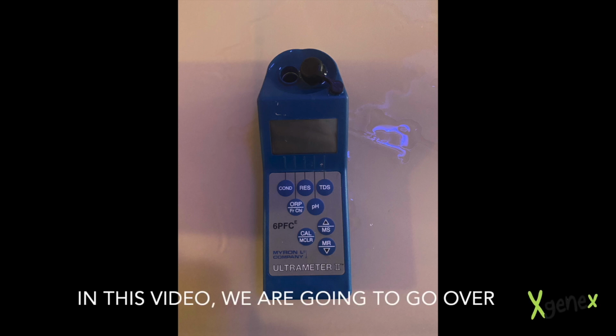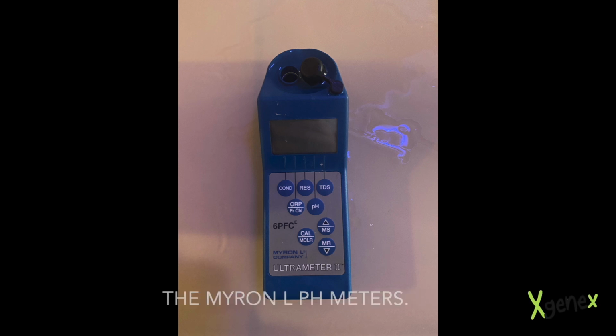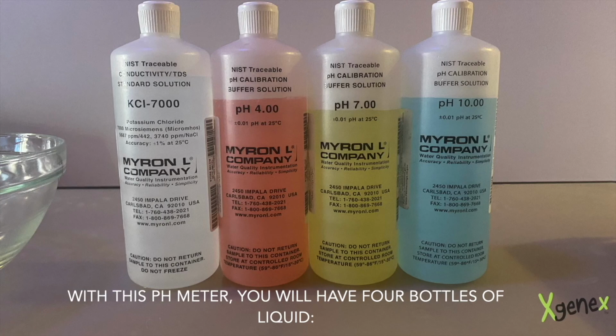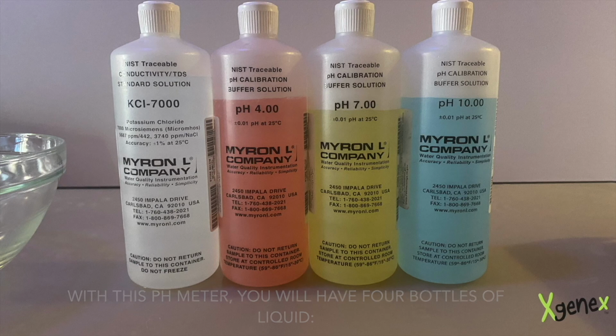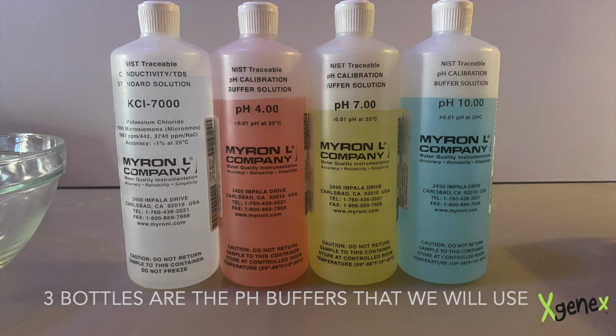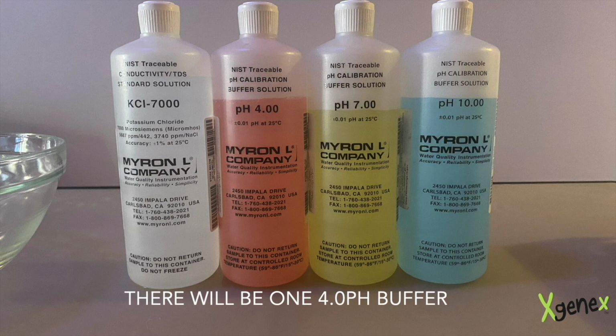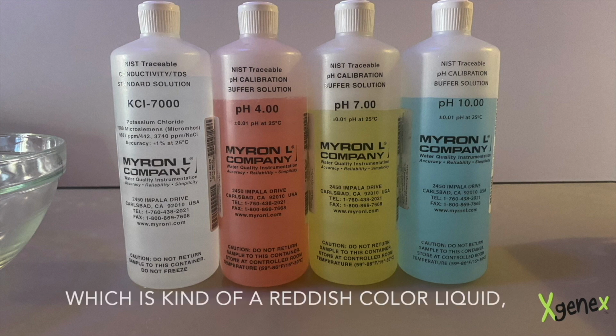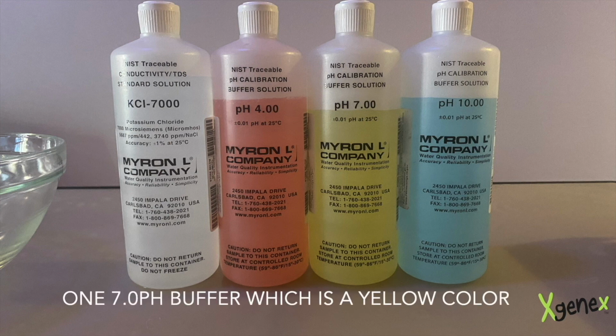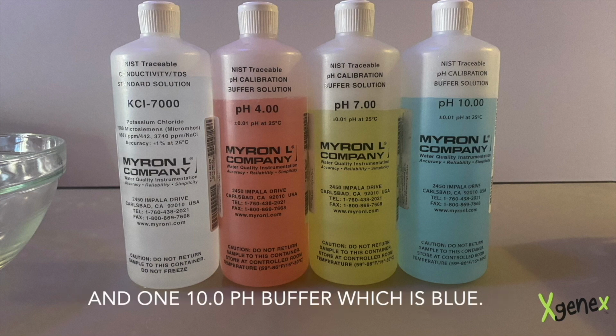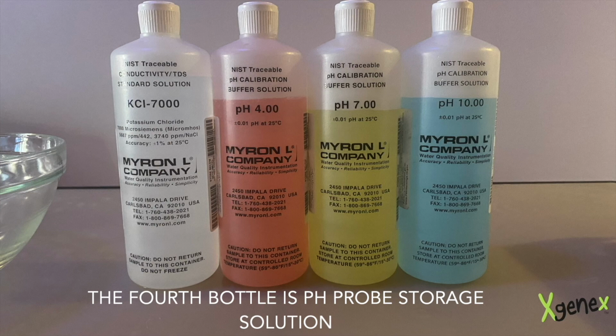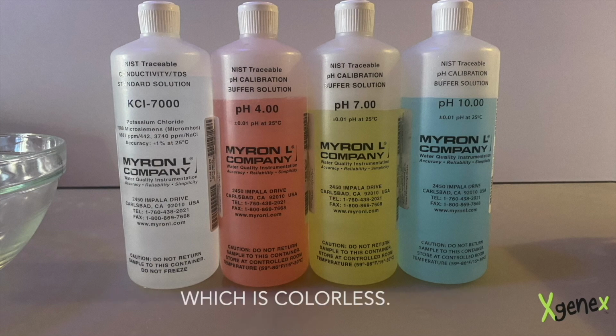In this video, we are going to go over how to properly calibrate and store the Myron L pH meters. With this pH meter, you will have 4 bottles of liquid. 3 bottles are the pH buffers that we will use to calibrate the meter. There will be one 4.0 pH buffer, which is kind of a reddish color liquid, one 7.0 pH buffer, which is a yellow color, and one 10.0 pH buffer, which is blue. The 4th bottle is pH probe storage solution, which is colorless.